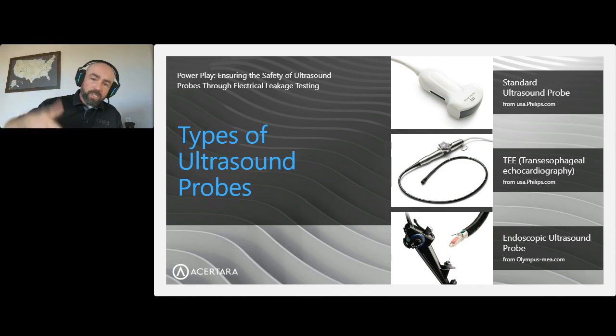But once that initial cleaning has been done, before you soak it in Cidex or use automated reprocessors or soak it in any of the other approved high-level disinfecting solutions, the electric leakage testing needs to be done, because if you find a problem in electric leakage testing at that stage, you can save the hospital from destroying the probe, right? You do the testing at that stage, then if it passes, you do the high-level disinfection. If it doesn't, then obviously you need to go talk to your biomed and figure out what your hospital's protocol is for the next steps to resolve that issue. So I hope that answers your question.